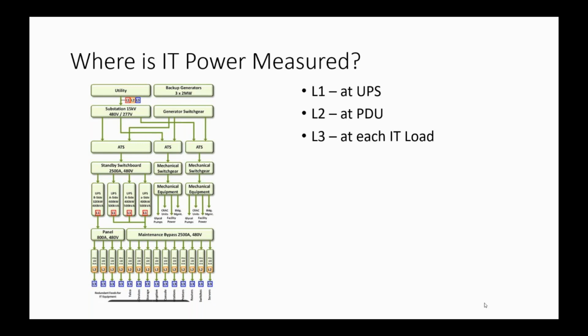And then the other one is that we don't want to lose track of this, and this diagram is a perfect one to explain it: we also need to be able to find the pathway of how the power is delivered. I've been working quite a bit in the Redfish models to ensure there are definitions for how to show the electrical connectivity from device to device, so that you can trace it. Mohan, if you put your pointer somewhere on that diagram, point to one of those L3 IT loads. Figure out where they are in that chain and how that gets bubbled up.